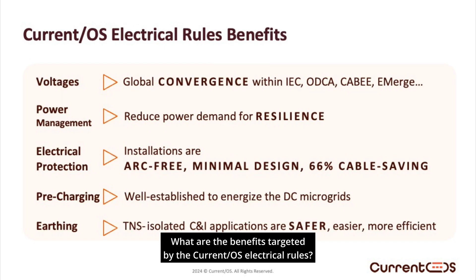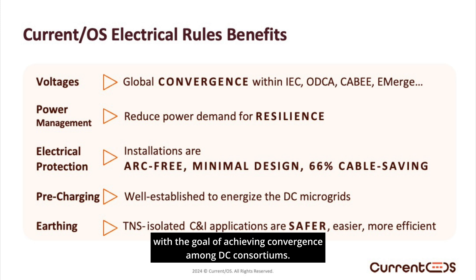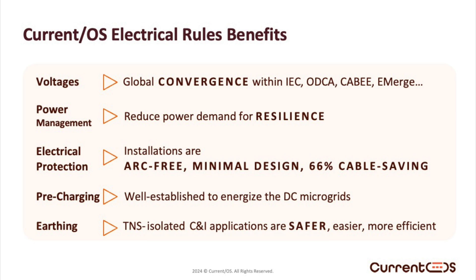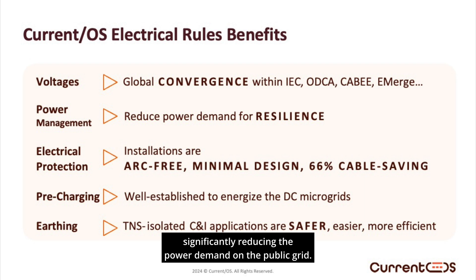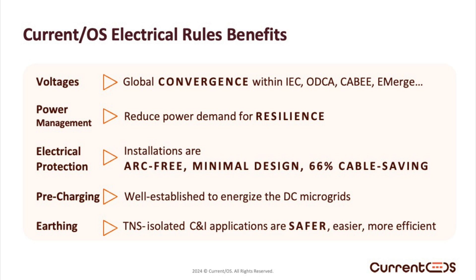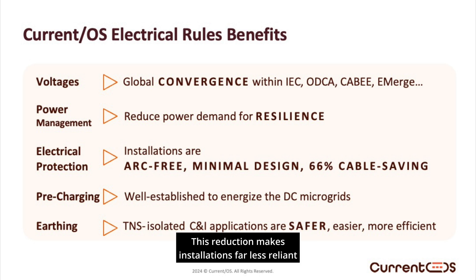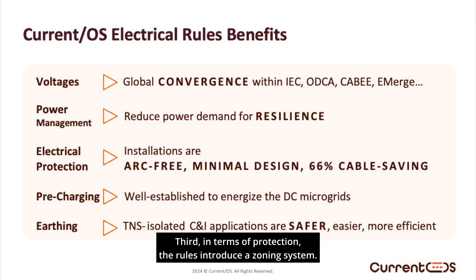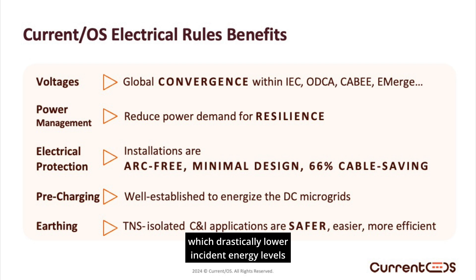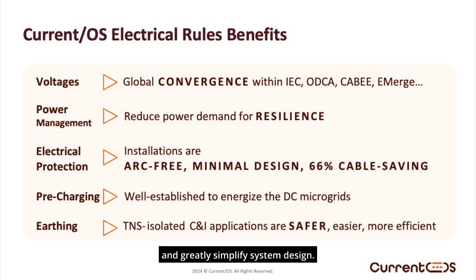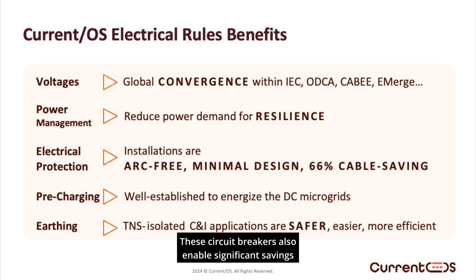What are the benefits targeted by the Current OS electrical rules? First, the rules define voltage bands — not just a single number — with the goal of achieving convergence among DC consortiums. Second, the rules address power management, significantly reducing the power demand on the public grid, making installations far less reliant on capacity availability from the public grid, while ensuring smooth integration with the AC grid. Third, in terms of protection, the rules introduce a zoning system. Current OS prioritizes the use of electronic circuit breakers, which drastically lower incident energy levels and greatly simplify system design. These circuit breakers also enable significant savings on cabling requirements across various applications.